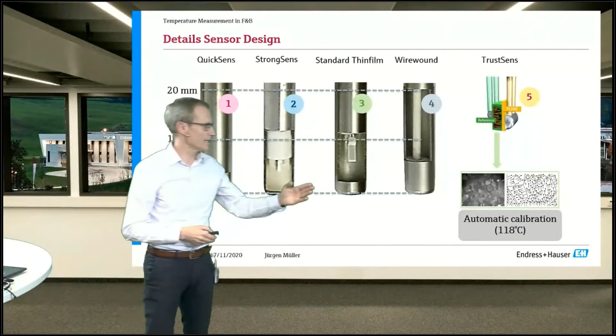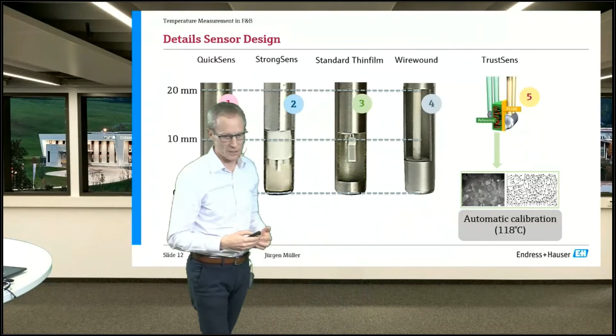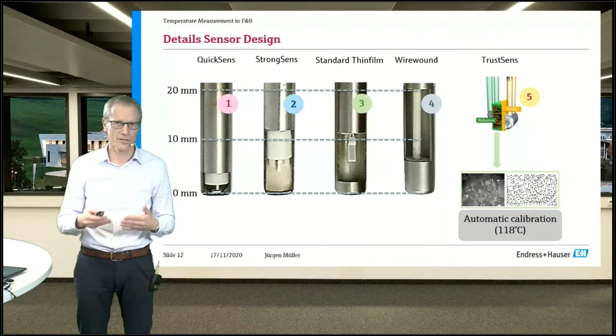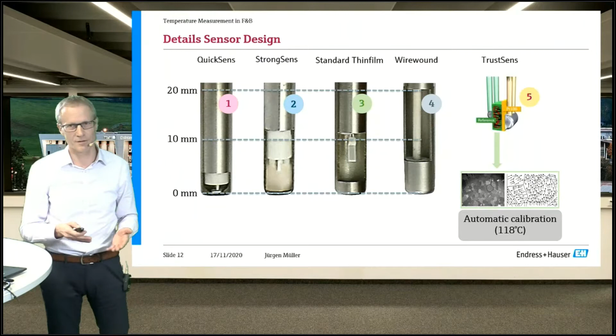Well, this triggering of the calibration is an effect of the so-called Curie point. There was a French physicist, Pierre Curie, who found out that there are special materials available, like in our case, the material that we use, that change their ferromagnetic properties at a certain temperature. So whenever this temperature is reached, the ferromagnetic properties change. We measure that. We measure the capacity of the reference material that we use. And when we see such a change in the ferromagnetic properties, the reference material is triggering the calibration.